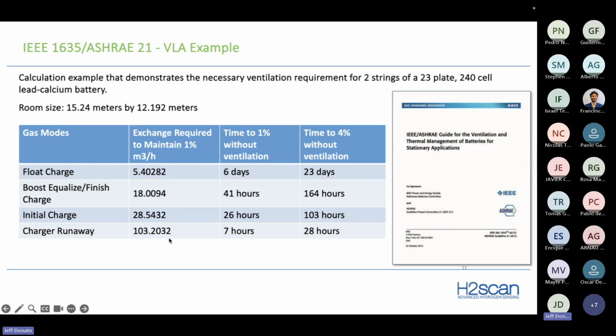And this is basically where hydrogen detection would come into play, because nobody's going to size a room with this kind of ventilation. So you would rely on your detection to see if there was any sort of anomaly like that going on. And as we know, most of the time, if you have any kind of event like this that creates that much hydrogen and it's a lead acid battery, pretty much shutting off the charger will remedy the condition. And so it'll stop the hydrogen from being produced and evacuate the room.